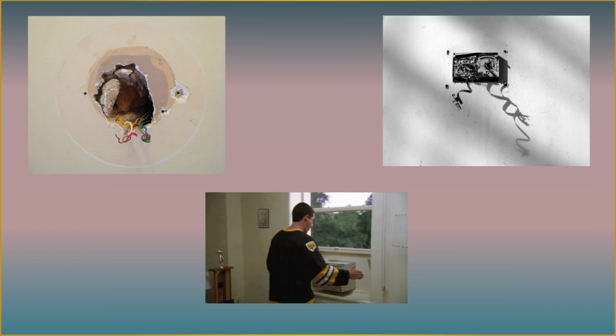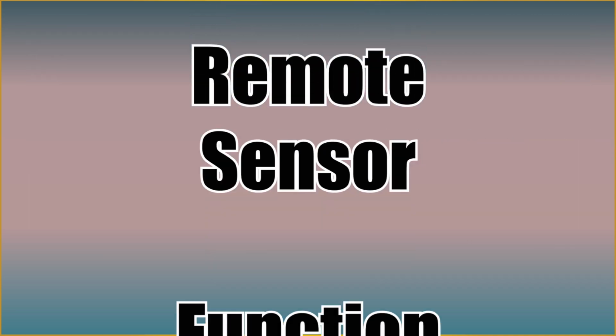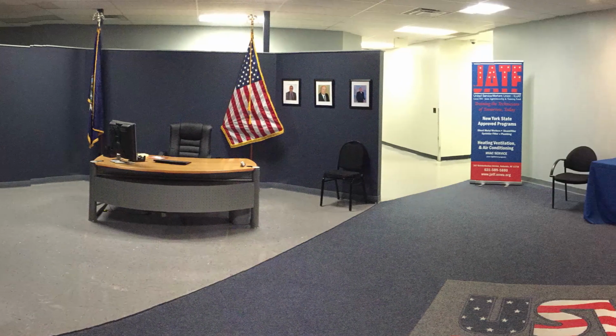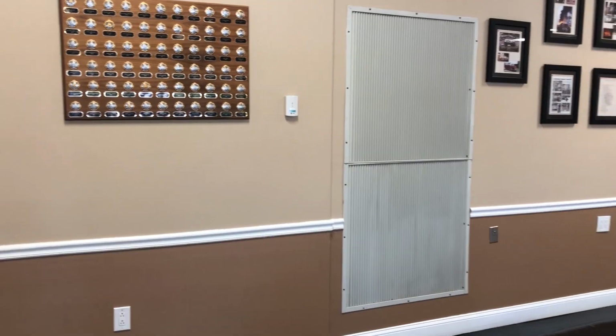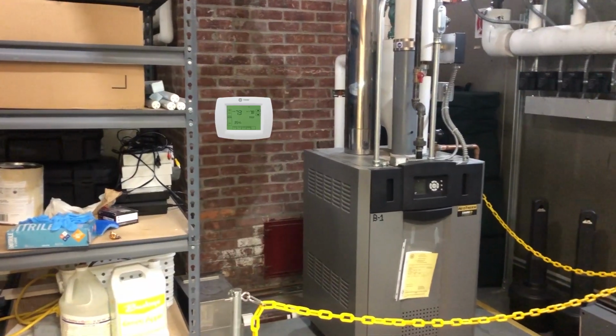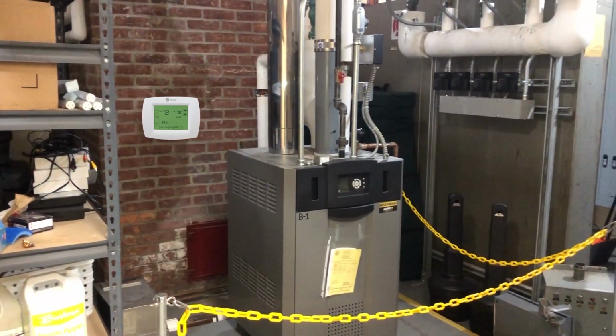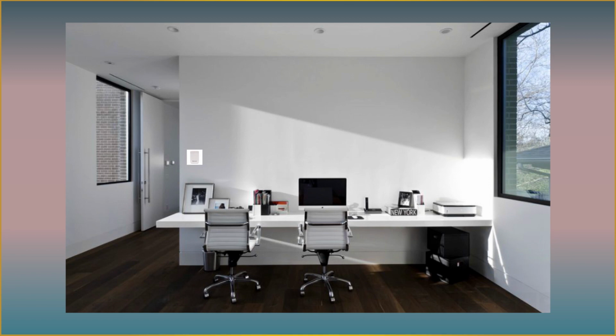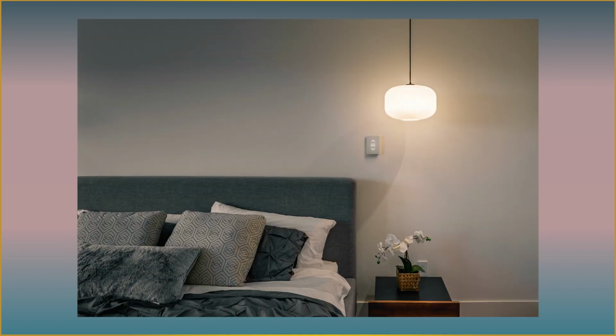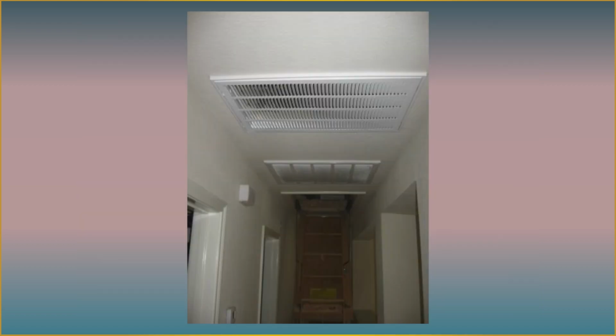The best way to combat this is to use the remote sensor function. If your thermostat has the ability, you can mount the stat in another room, office, closet, or mechanical room. Then just run a wire from the new secure thermostat location to another suitable location in the space and just mount the temperature sensor. Nice and easy. It's also perfect for homes as well. You can mount the thermostat in the master bedroom and install the remote sensor near the return grill.